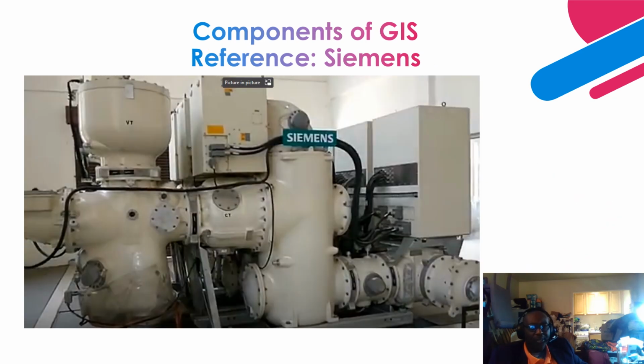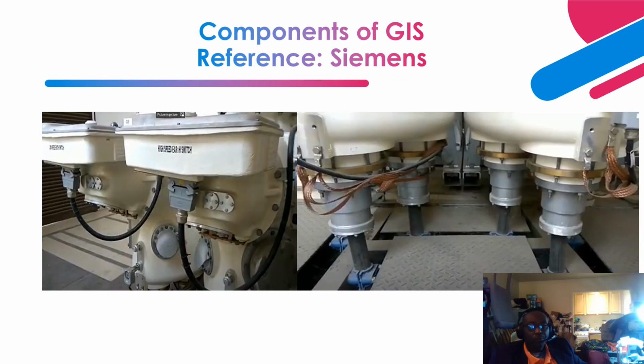From here. Okay, so I showed you a picture of this earlier, and I showed you all the components of it, and basically how all of them are wired from each component to your LCC cabinet. And I also showed you your line side cable feeders. One of the things that I want to talk about is your high-speed earthing switches, right? Okay, I indicated that sometimes if you have a lightning surge, an external lightning surge, that basically intrudes on the line side, there are high-speed earthing switches that take those charges or high voltage to ground as fast as possible, right?